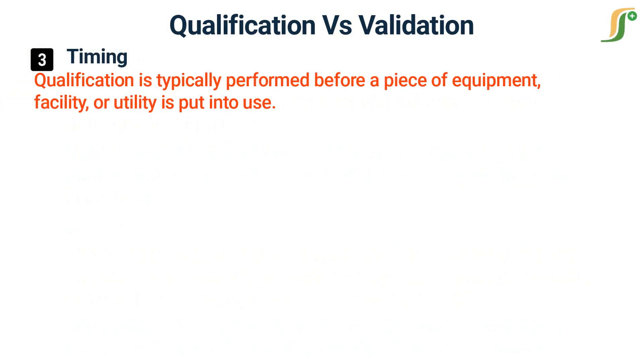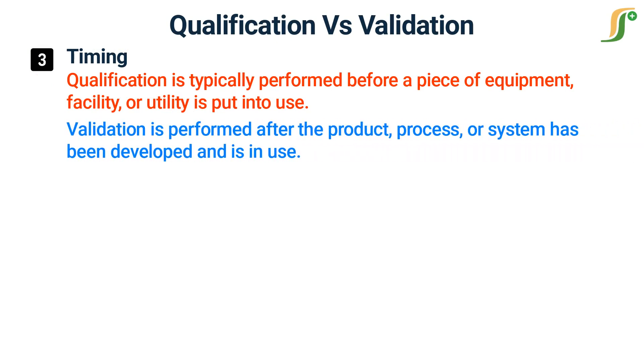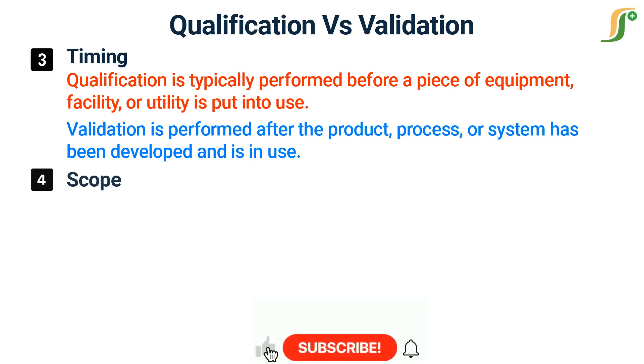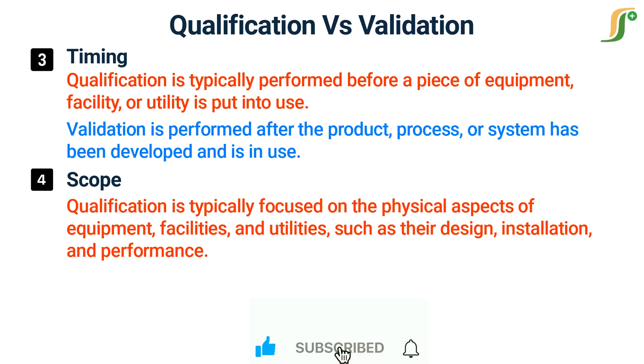Qualification is typically performed before a piece of equipment, facility, or utility is put into use. Validation is performed after the product, process, or system has been developed and is in use. Qualification is typically focused on the physical aspects of equipment, facilities, and utilities, such as their design, installation, qualification, and performance.